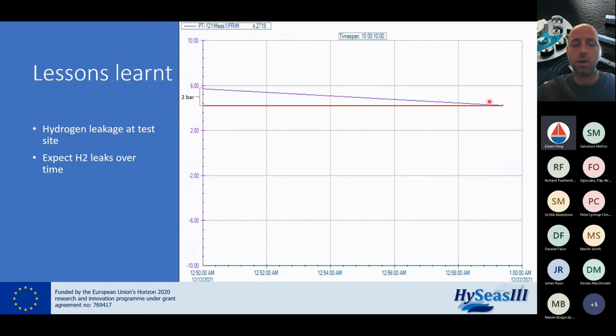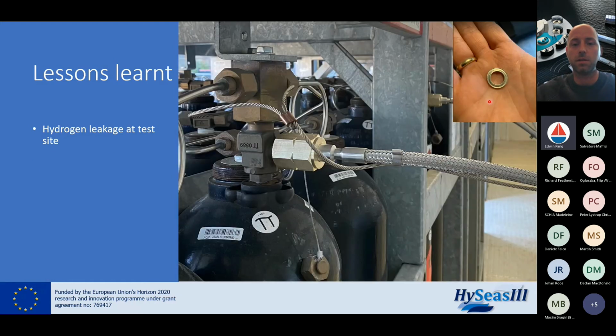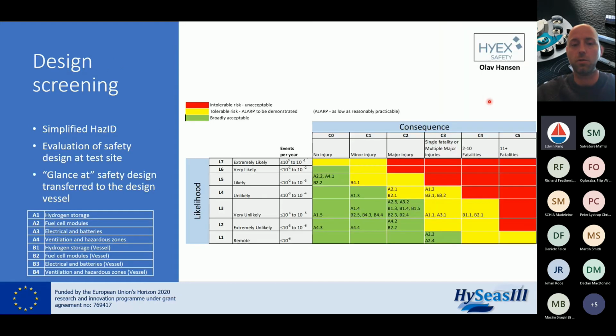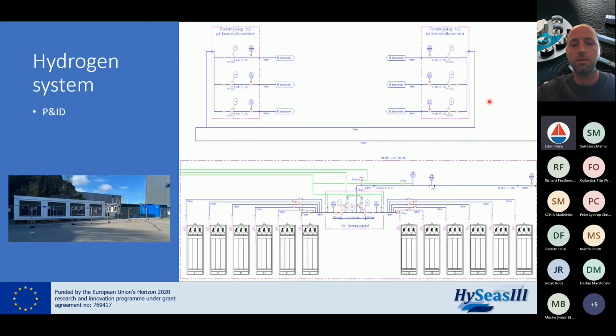We also installed something after this incident of the big leakage. I will just go back to the P&ID. In the middle here, it's not visible, but this is a pressure release where we can do a manual release. So when we left the site, we closed all the valves, and we released the fuel pressure from around 15 bars to below fuel gas pressure, which was 8 bars, and we minimized the leakage over time in the fuel lines. That was when we left the site, to avoid this.